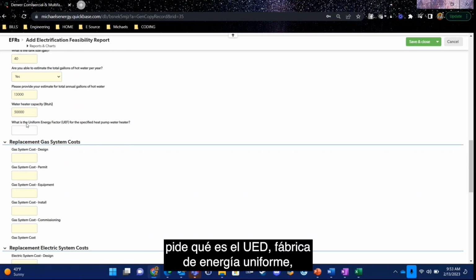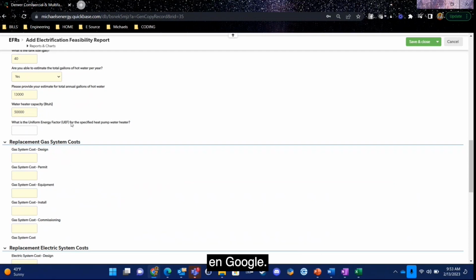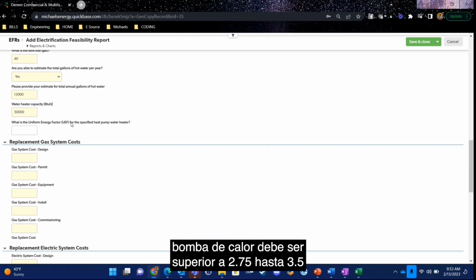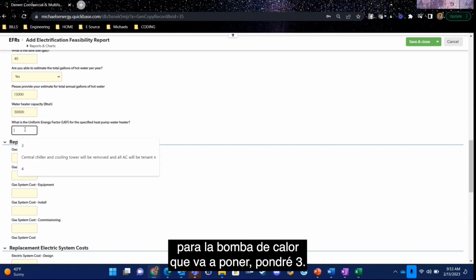Now you're asked what the UEF, that's the uniform energy factor. Usually you can find this on a spec sheet or doing some Google searching. A heat pump hot water heater should be above 2.75 up to 3.5, maybe even higher. But you're just looking for that UEF for the heat pump that you're going to put in. I'll just put 3.2.